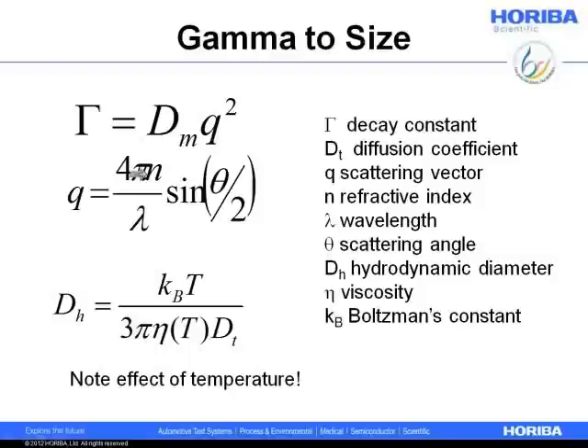The decay constant gamma relates to the mutual diffusion coefficient D and q-squared, where q is a scattering vector summarizing the scattering angle, wavelength, and refractive index of the liquid. The hydrodynamic diameter is then found from the Stokes-Einstein equation: D equals k_B times T divided by (3π times η times d_H), where k_B is Boltzmann's constant, T is temperature, η is viscosity, and d_H is hydrodynamic diameter. Note the strong effect of temperature on suspending medium viscosity — something to be very aware of when making measurements.